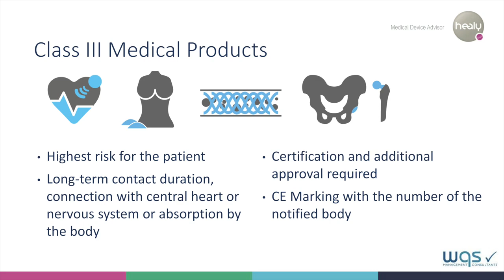In order to carry the CE mark, manufacturers and their products must meet a number of strict requirements. These requirements include classification into one of the risk classes we just discussed, as well as compliance with all requirements of the Medical Devices Act. Proof of a risk management policy and detailed technical documentation of the product must be present. Additionally, a quality management system in accordance with the relevant standards must be implemented.